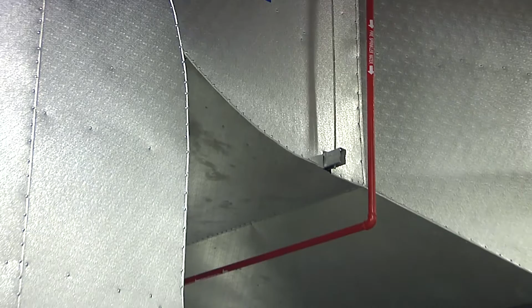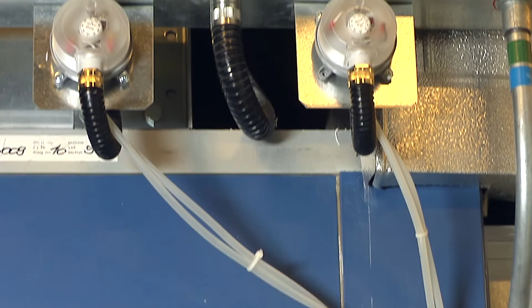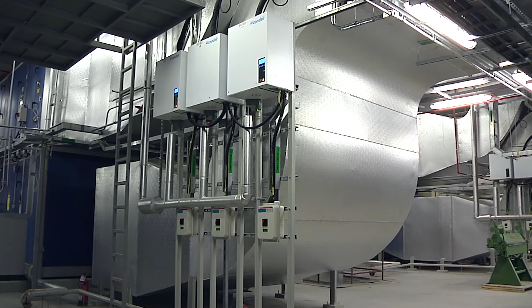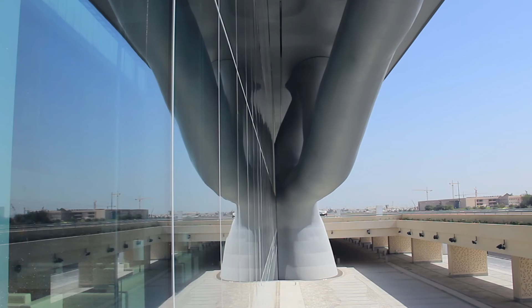The reduced duct length contributes to energy efficiency by reducing fan horsepower as well as minimizing supply air temperature losses. The facility, in addition to its geometry, presented a temperature and humidity control challenge due to the large building population occupancy extremes. The heating, ventilation and air conditioning (HVAC) systems were designed such that they would adapt efficiently to the people occupancy, lighting and electrical load variation from minimal to the maximum of around 7,700 people expected to be present at any one time. In addition, the HVAC system reacts almost instantly to the outdoor condition variations imposed by the solar effect on the various perimeter exposures at different times of the day.